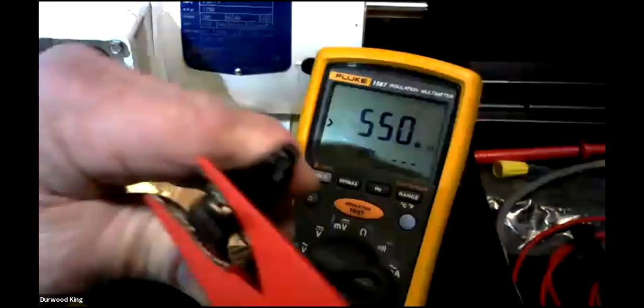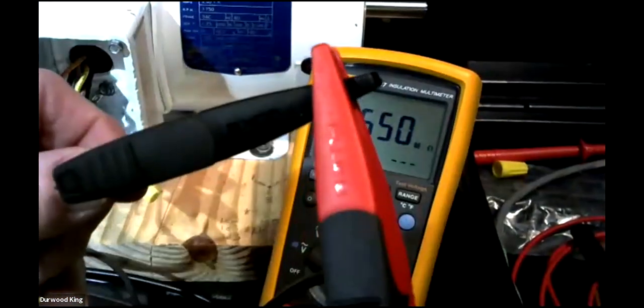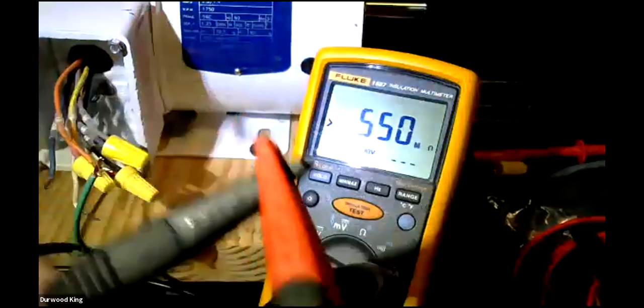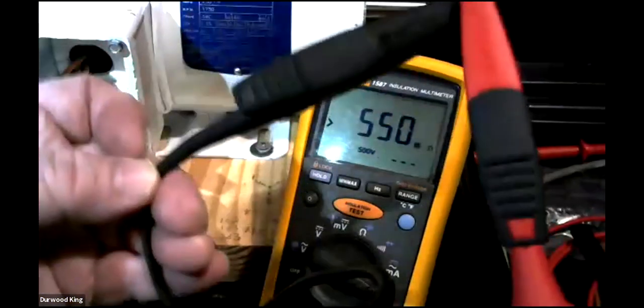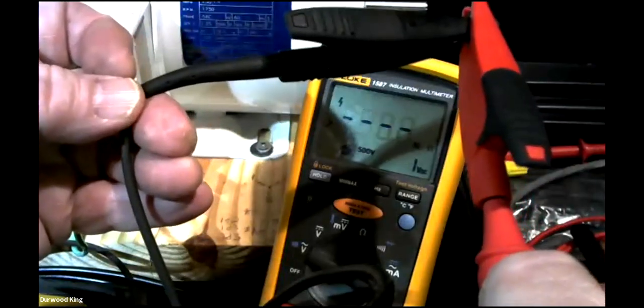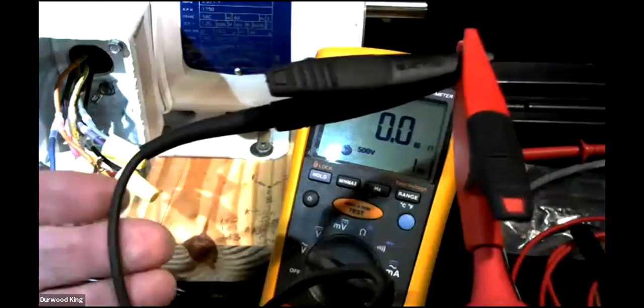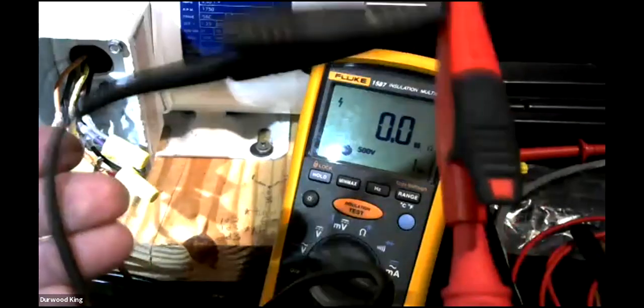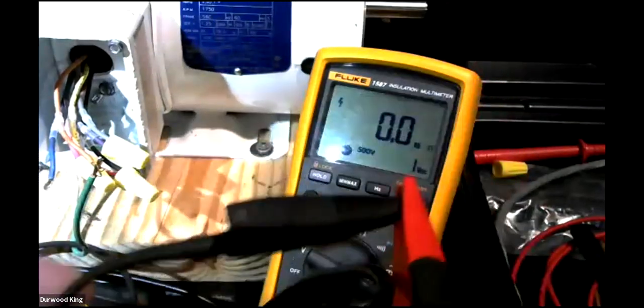Now, the next step to test a meter is this. Short the wires together like this. Put them together like that. You want to do a dead short circuit test and see, does this say 0? So you put them together and hit the button like this and watch. Look at that. What does that say? 0.0 megohms. Now that's a dead short in a motor. It could read that low. That's bad, okay? Because you don't want a connection between a hot wire and ground, right?